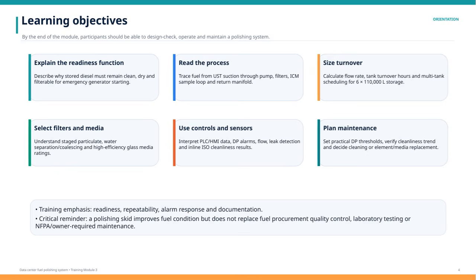Maintenance planning is key, so we'll set practical differential pressure thresholds, verify cleanliness trends, and determine when cleaning or media replacement is necessary. Throughout the training, we emphasize readiness, repeatability, alarm response, and thorough documentation. Remember, while a polishing skid improves fuel condition, it doesn't replace the need for rigorous fuel procurement quality control, laboratory testing, or the maintenance mandated by NFPA and the owner. This comprehensive approach ensures your data center's fuel system stays reliable and in top condition.